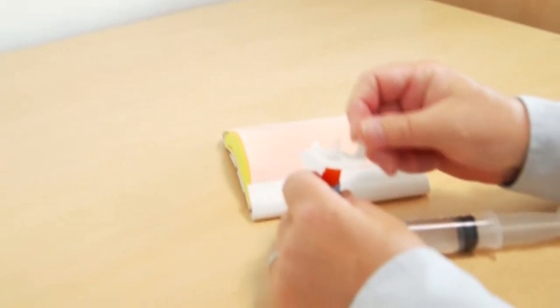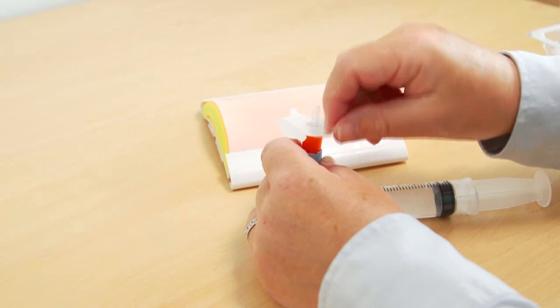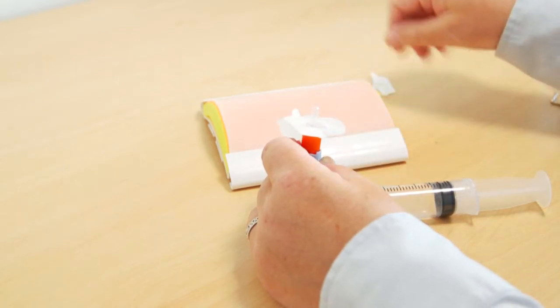Once the infusion set is primed, it can then be connected to the infusion pump or inserted to the patient, depending again on local procedures. Before insertion, it is important to ensure that the infusion site has been prepared according to local procedures. Once you are ready to insert the device, first of all, remove the paper covering by gently pulling away from the tape.